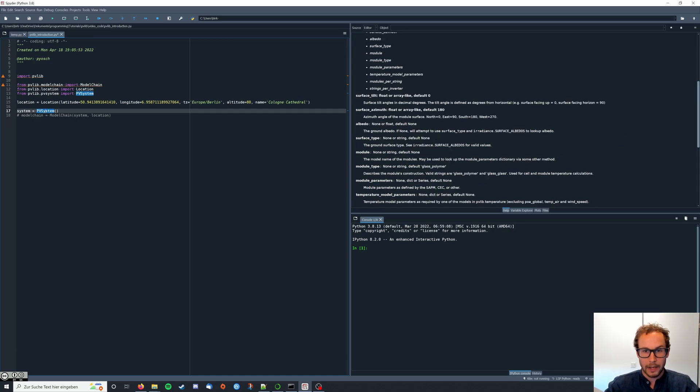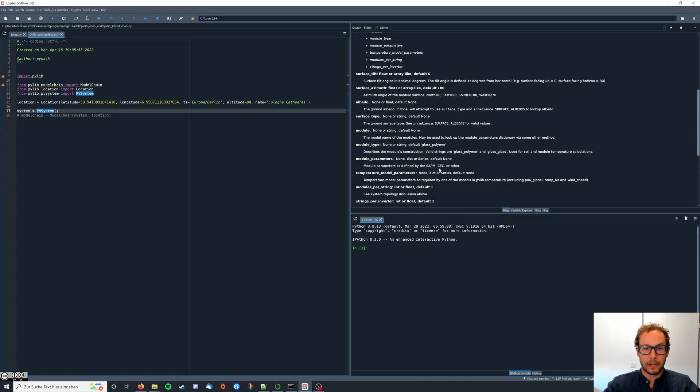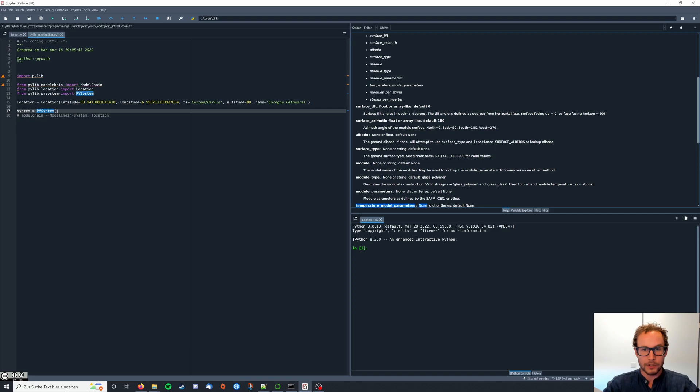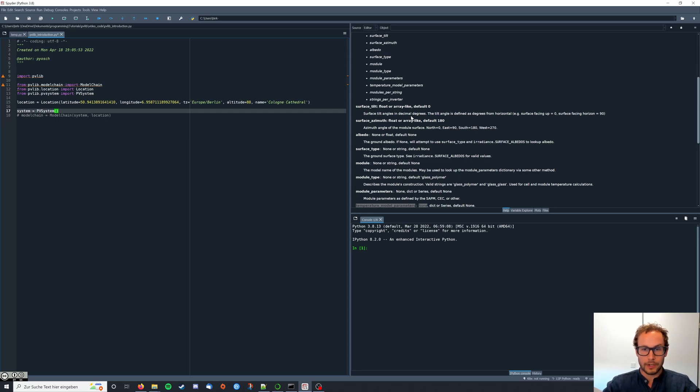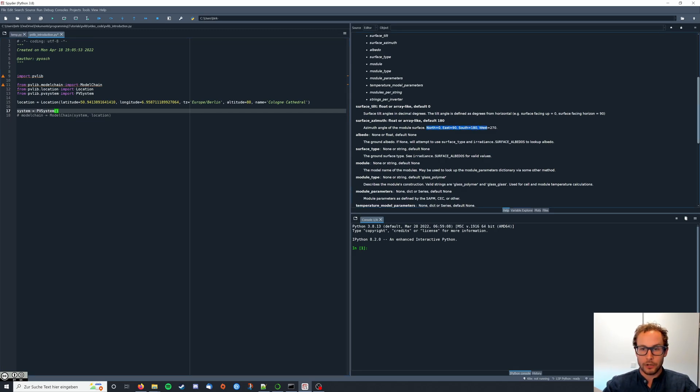We will need information about the PV modules we want to use, the inverters, the orientation, and the so-called temperature model. I'm going to start with the orientation. The surface tilt is the first thing I'm going to enter and after that the surface azimuth. The surface tilt tells us at which angle the PV module is installed and the surface azimuth tells us in which orientation our PV module is installed.